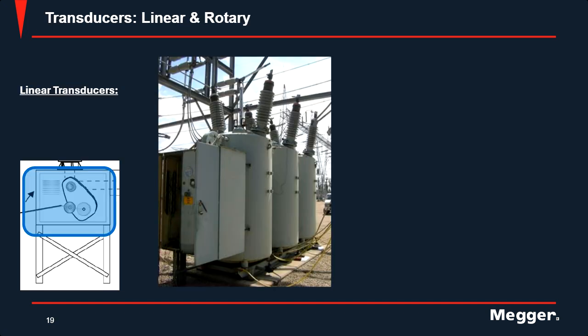Now, as you heard me mention earlier, there are all different transducers out there. There's linear and rotary. So the contact travel motion is captured by connecting a travel transducer to the moving parts of the breaker's operating mechanism. This transducer can provide analog voltage relative to the movement of the contact. The motion is then presented as a curve, as I said, where distance and time allows for further analysis.